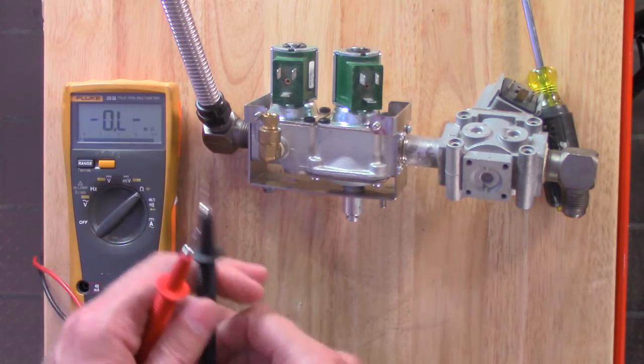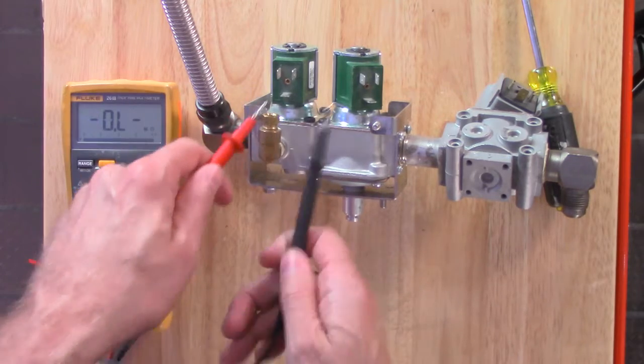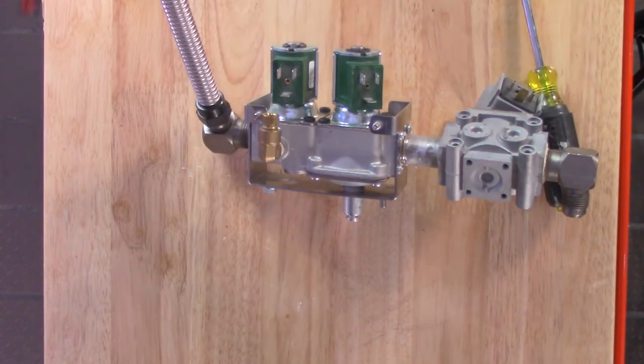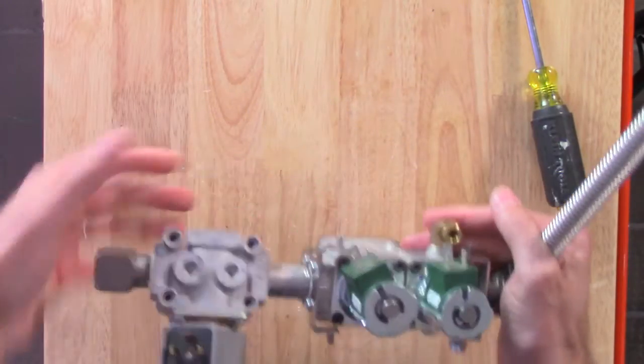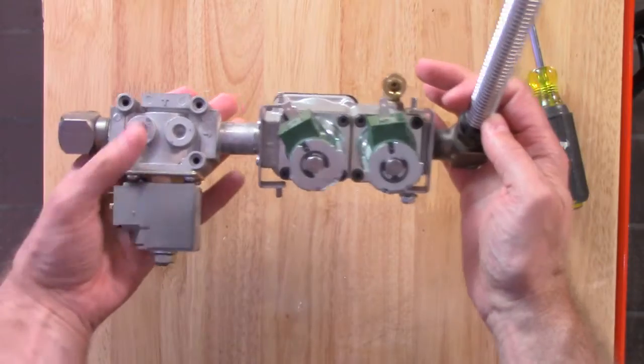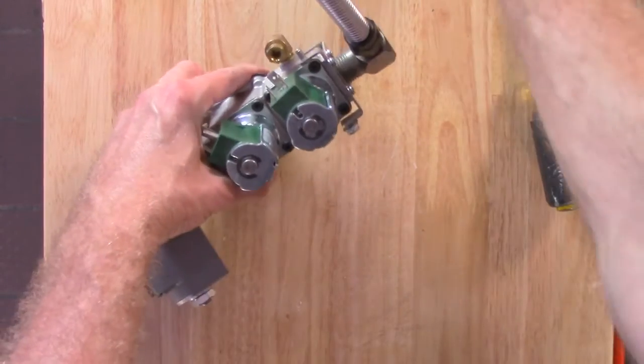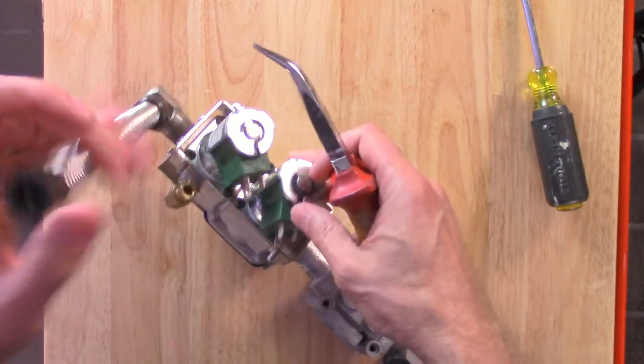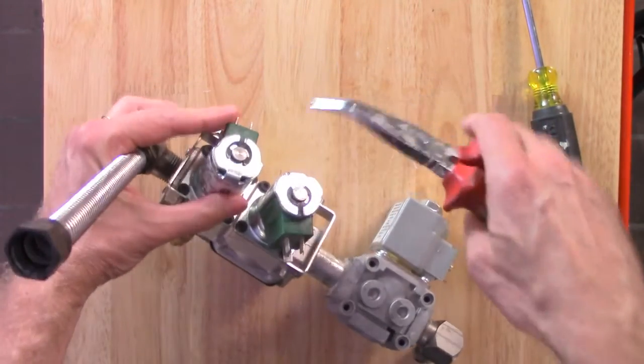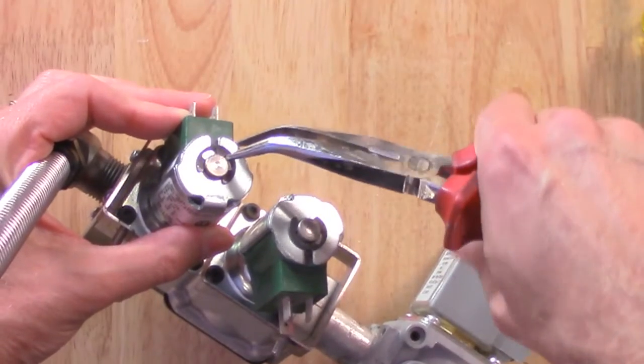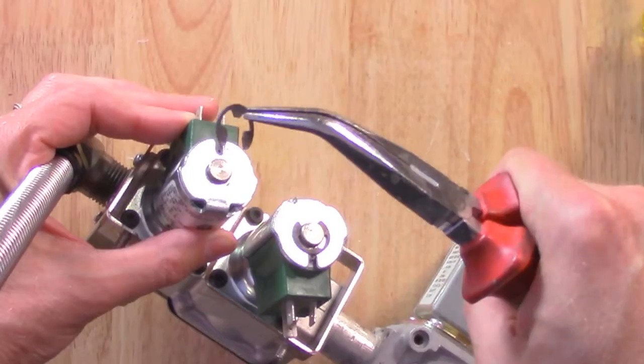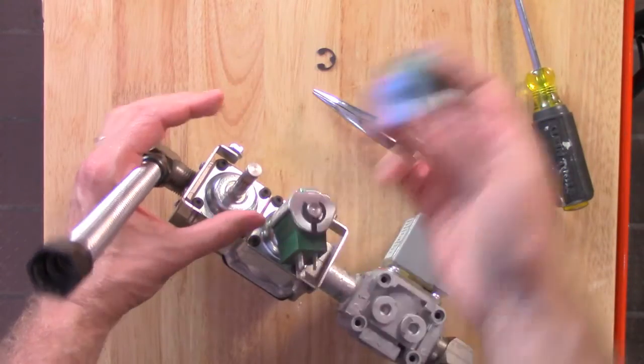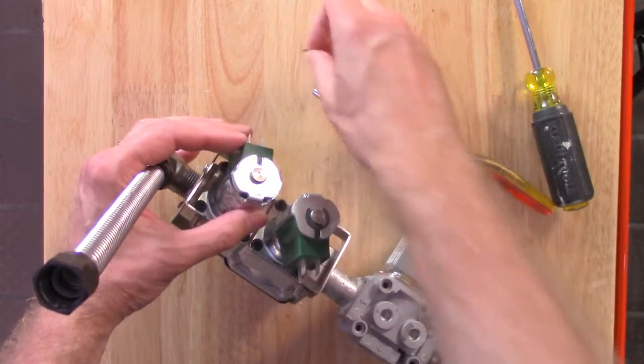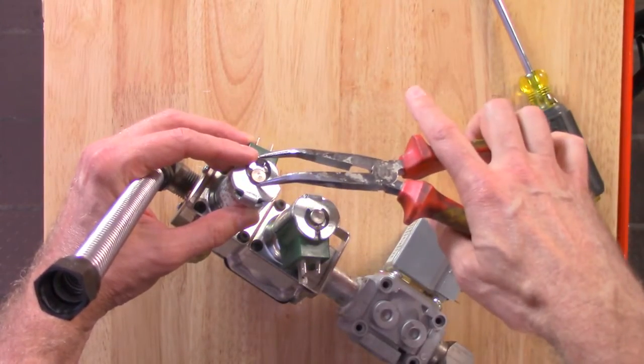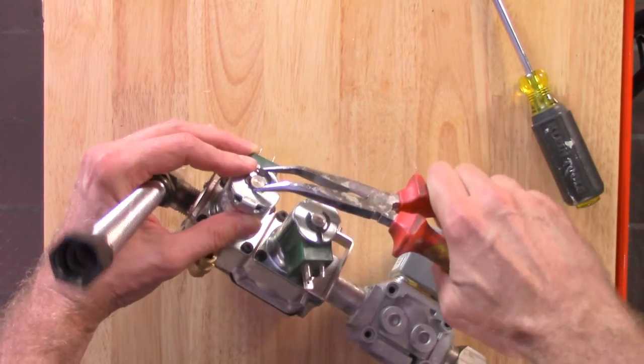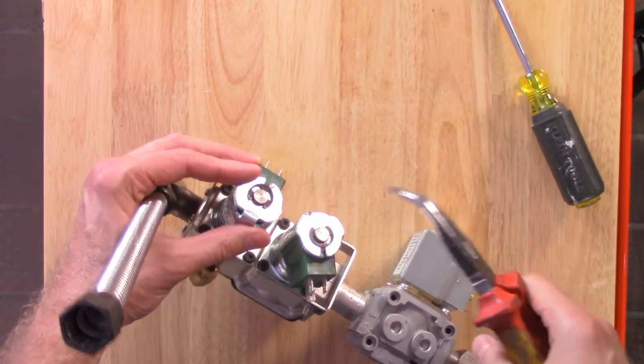Really, what you want to look for to find out if it's a bad coil before you go to replace it is that it would probably read open. Now let's say you do have a bad coil for your main burn. This is how it's going to set in the fryer, like so. What you could end up doing is needing to replace the coil. I'm going to try and pull that clip off. I get the clip off, remove the bad coil, get the new one, put it on, get my clip right here, give the arc clip a little bit of a squeeze, get it in place, and then we're good to go.